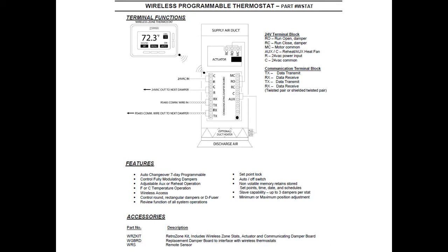Each zone thermostat is synced with its respective modulating zone damper. At each stat, you can initiate auxiliary heat, either reheat or baseboard, along with a 2 to 4 degree deadband to initiate the supplemental heat operation. A calibration feature, along with energy savings mode, are also available on each stat.